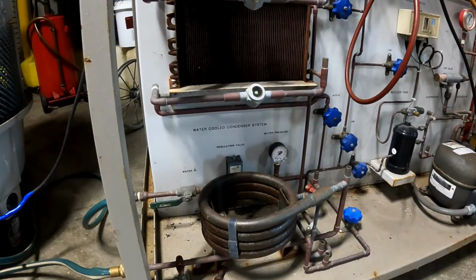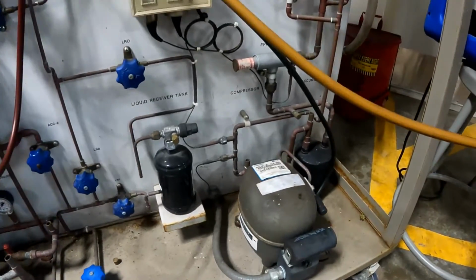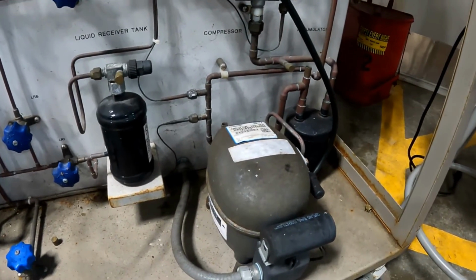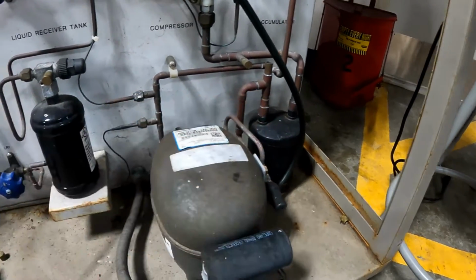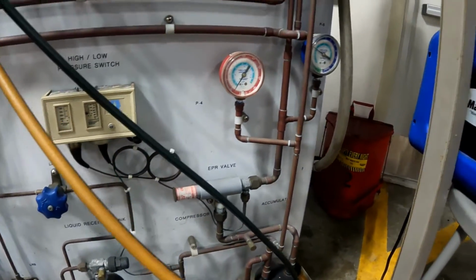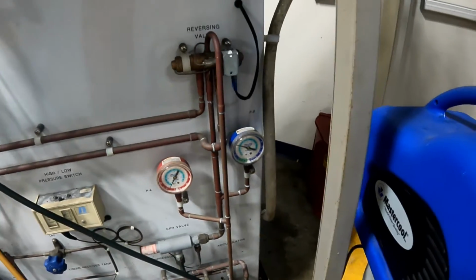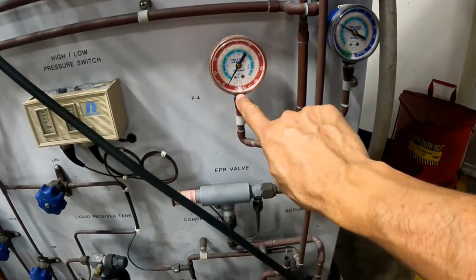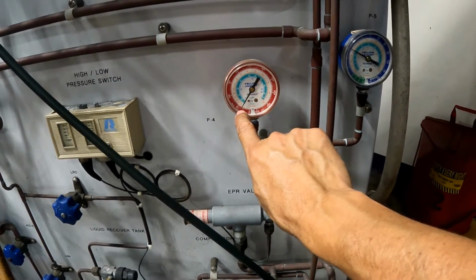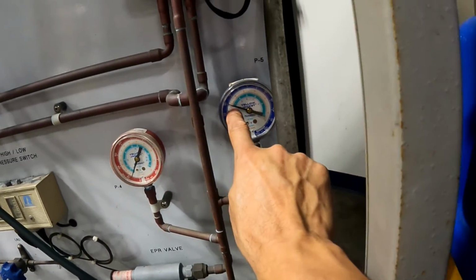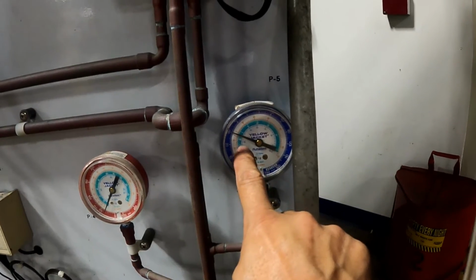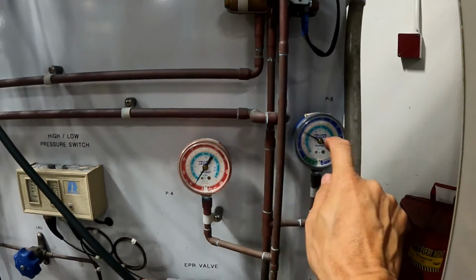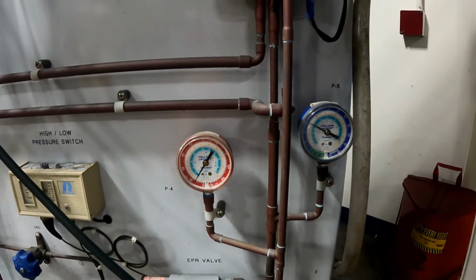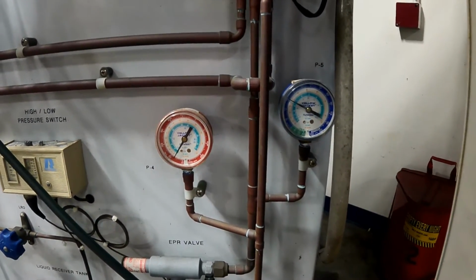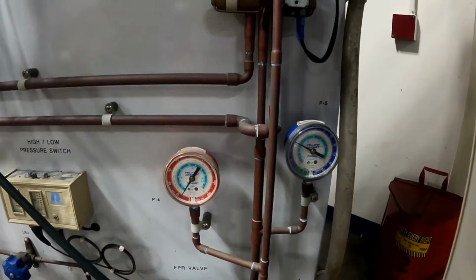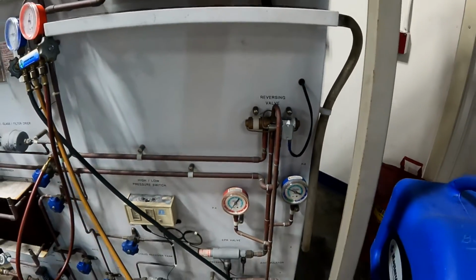Those types of condensers. The compressor is a hermetic compressor, and we have the high pressure side and the low pressure side. And in this particular example, we have a low level of refrigerant. On the high pressure side we only have 30 psi, and exactly the same 30 psi on the low pressure side. In both sides we have a low pressure. For that reason, today we are going to recover that refrigerant. We are going to do the vacuum, and after that we are going to charge the system again.